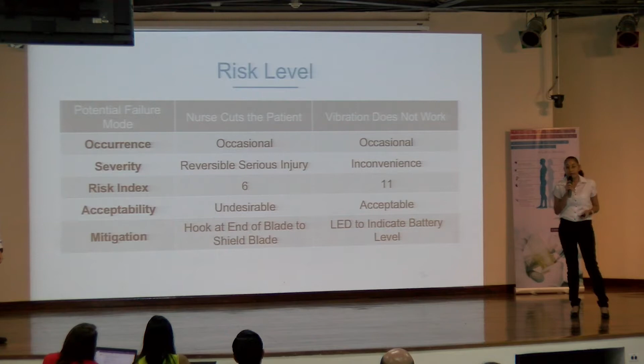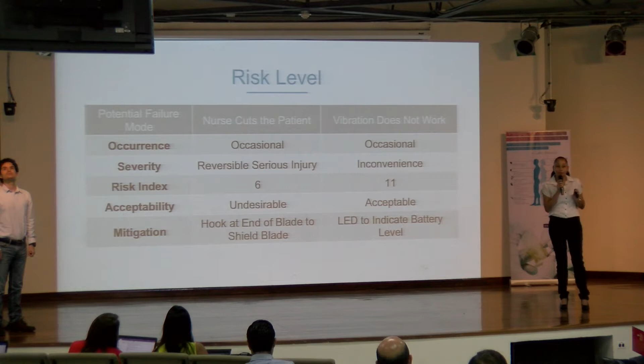Another potential failure that we found is if the vibration doesn't work. This can be caused if the battery dies. This is acceptable, and the mitigation plan that we created is an LED that indicates the battery level. So the green color indicates that you have 100% of battery. The yellow color indicates that you have 50% of battery, and the red color indicates that you only have 10% of battery left.